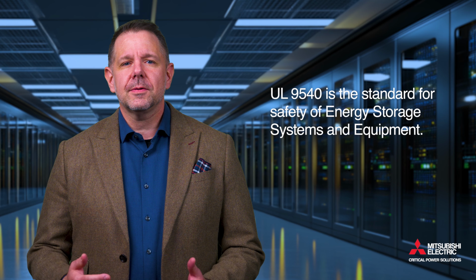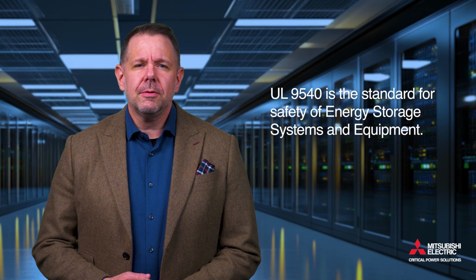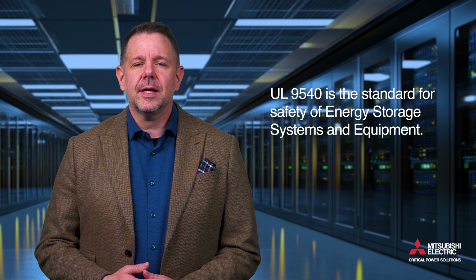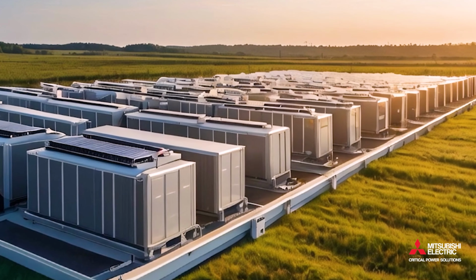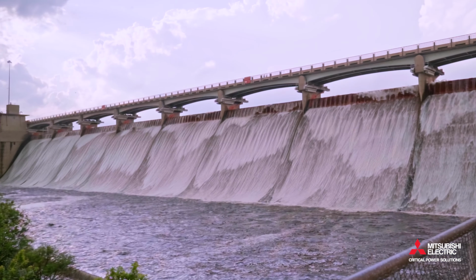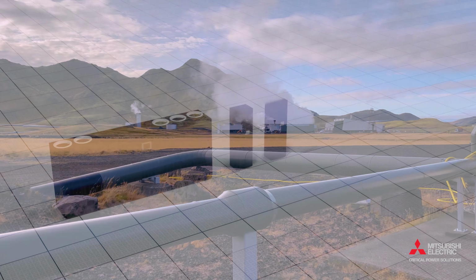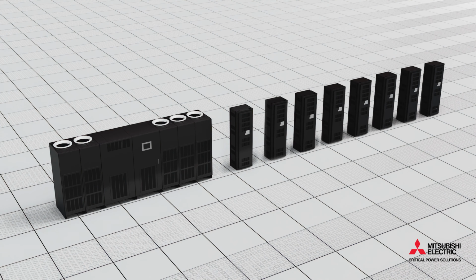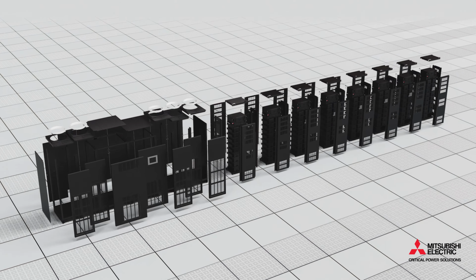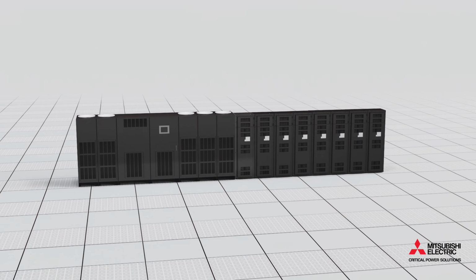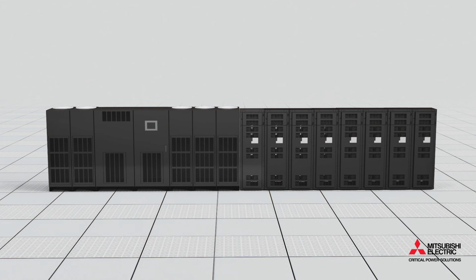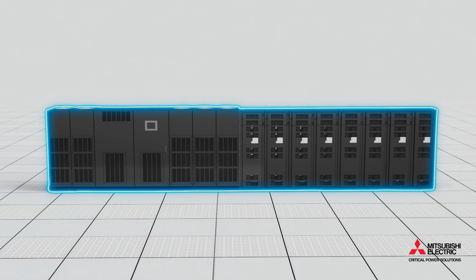UL 9540 is the standard for safety of energy storage systems and equipment. UL 9540 can cover a variety of types of systems from electrochemical, chemical, mechanical, or thermal. UL 9540 is also a system listing, meaning that individual parts and pieces of equipment are not considered to be UL 9540 listed on their own. To obtain UL 9540, the energy storage system must be evaluated and tested for compliance with the standard.